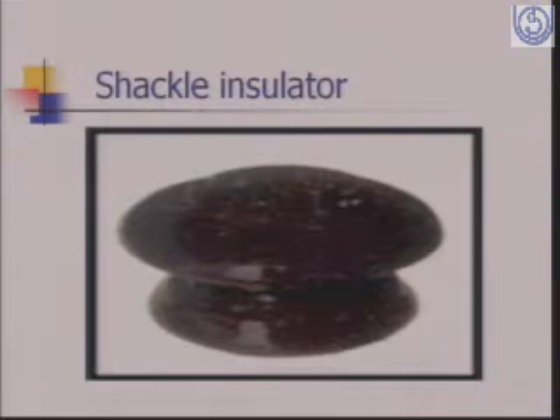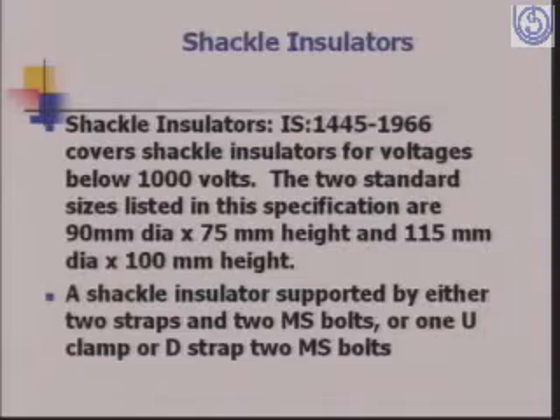This is the example of a shackle insulator. The picture is not very clear, but this is how it looks. Then these shackle insulators are according to IS 1445, which covers insulators for voltages below 1000 volts. The two standard sizes listed in the specification are 90 mm dia and 75 mm height, and 115 mm dia and 100 mm height. And a shackle insulator supported by either two straps and 2 MS bolts, or one U clamp or D strap and 2 MS bolts is used.